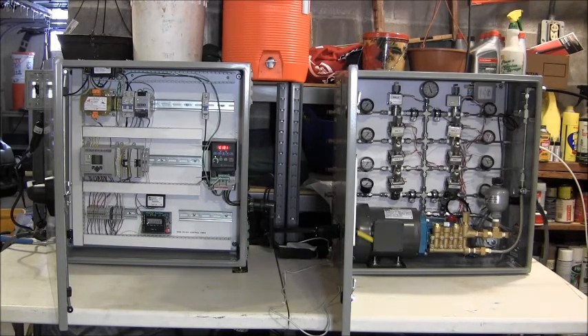The other thing that's going on here is that this microcontroller is actually monitoring a lot of this package. It's monitoring the output pressure through a pressure transmitter. It's monitoring the incoming pressure over here on the right to make sure that there is a water supply coming into it. It actually has a temperature monitor up here in the upper right hand corner. It monitors the temperature of the pump panel just to know whether it is in some extreme environments and to know what the temperature is inside. And then it also has a water sensor down here at the bottom that actually senses if there's a major leak within the control panel, and it will shut it down.